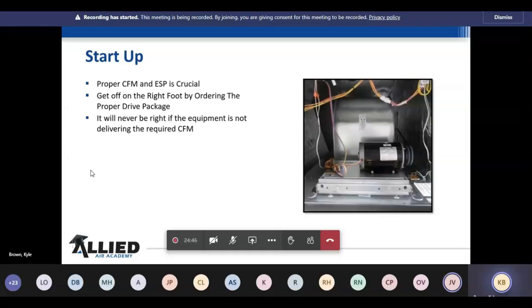Okay. A lot of times we get into the mindset of, oh crap, we only have 2 hours to get this back up and running, especially in a hospital setting. And I hate to say this, but in a bar setting, those are the two places that panic the most when they don't have air conditioning. And we don't think about what CFM and what static pressure. Next week, I'm going to talk a little bit more about drive kits, but making sure that the static pressure and the correct drive kit are in the unit is crucial.